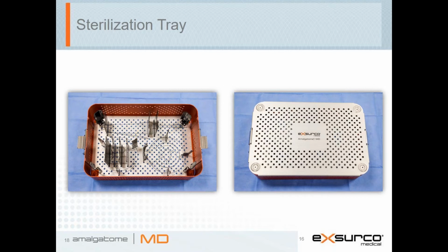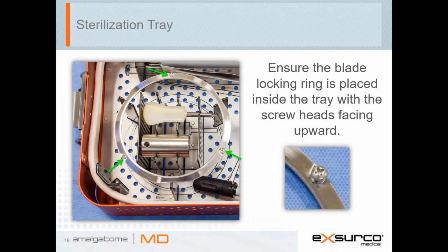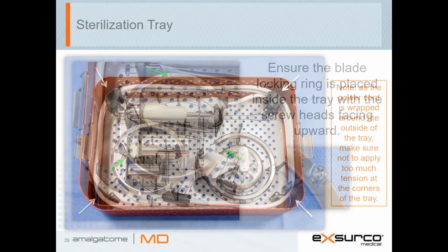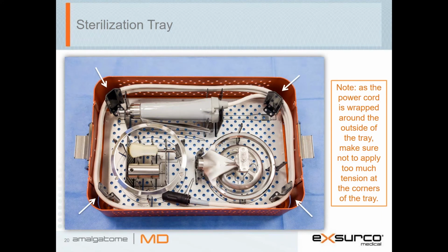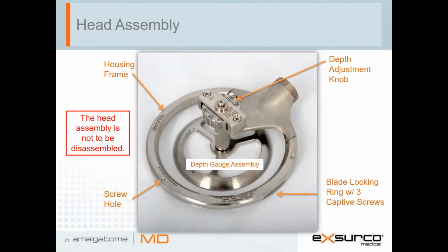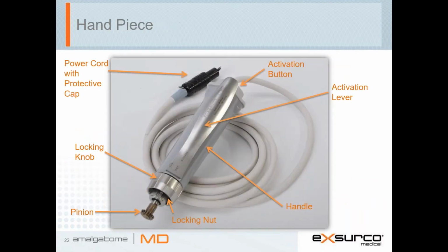Sterilization tray. Inside the tray are pictures where each component should be placed for sterilization. Ensure the blade locking ring is placed inside the tray with the screw heads facing upward. Ensure the power cord is wrapped around the brackets located on the outside of the tray. Head assembly. The Amalgatome MD head assembly is validated to stay together at all times. Leave as is and do not disassemble the knob or any of the associated parts. Taking apart the Amalgatome MD head assembly could cause the device to not function properly.